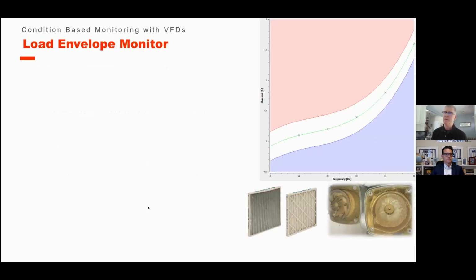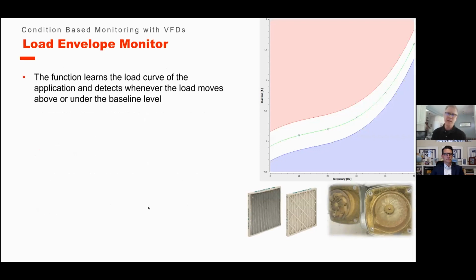The load envelope, the function of it, is that it learns the load curve of the application, and it detects wherever that load moves above or below the baseline level. So as we're looking at a machine and we're looking at the load values, it's very important, because as things start to wear and degrade, our load increases. And we want to know this. We want to know it ahead of time so we can catch problems before they become catastrophic, with extreme downtime and extreme cost.